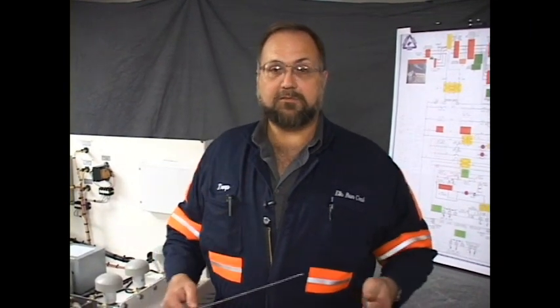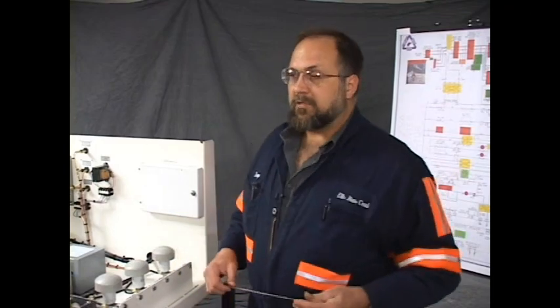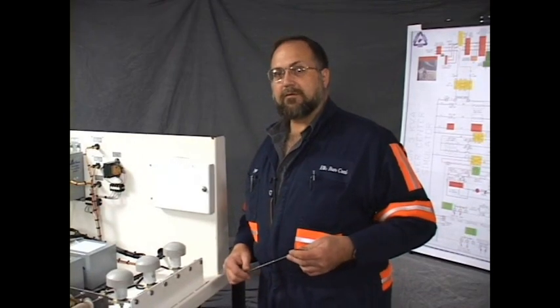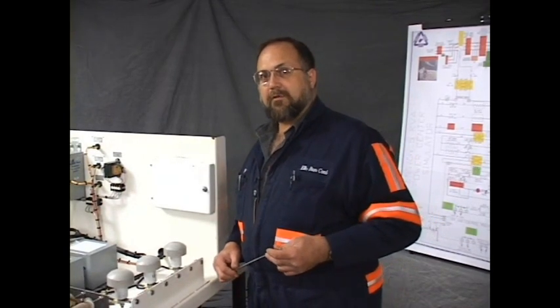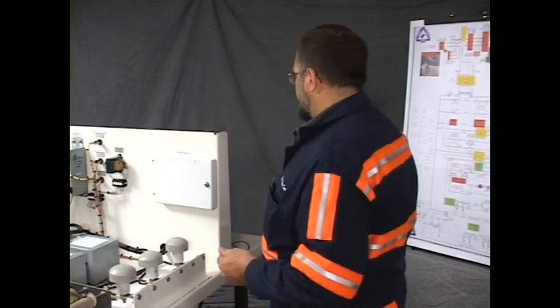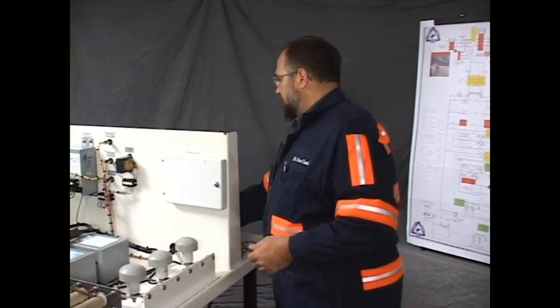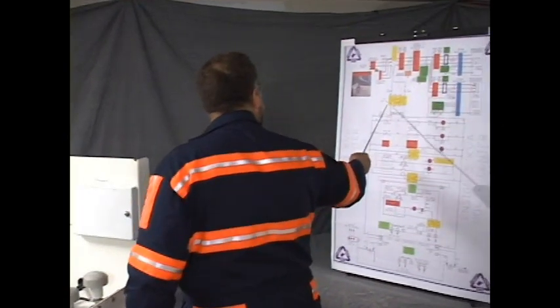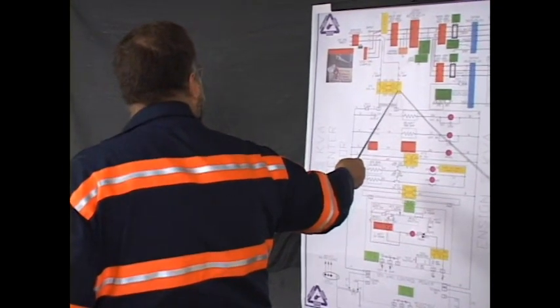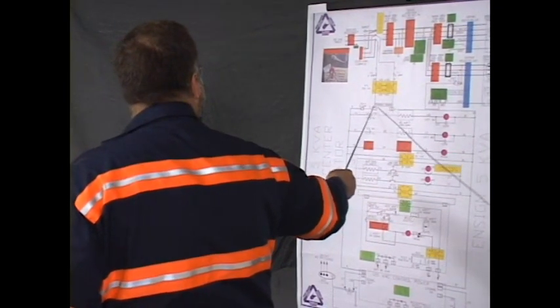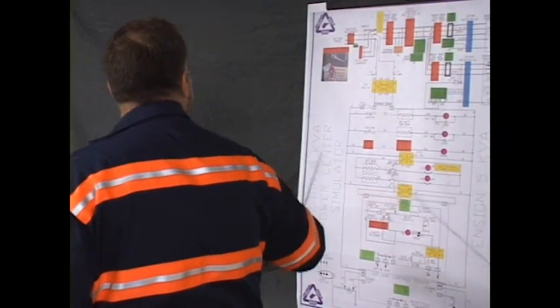There's a lot of information to be gained from the written card. It says the primary is energized, but none of the control circuit. The last place we know we have power is at the primary. So we'll begin with a continuity test on the secondary of KT1 and follow those circuits out. Secondary of KT1, X4 and X1 are the terminals involved, to a terminal board, and then to the fuse.